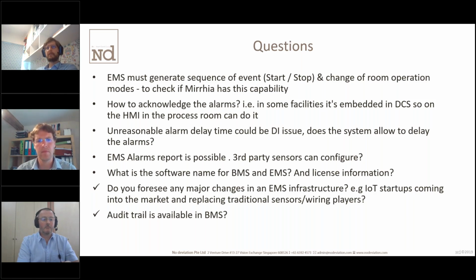Unreasonable alarm delay time could be a DI issue, totally agree. Does the system allow the delays of the alarm? Nicolas, can you delay an alarm in Mirrhia? So can we delay an alarm? We can have a delay. So we can say, for instance, that for the pressure or any kind of sensor, we can have a delay. This is something that I've shown in the demo. So you set your threshold, and let's say that you have a pressure sensor there. You can say that there is a delay of 30 seconds, and you won't have any alarm during the first 30 seconds.